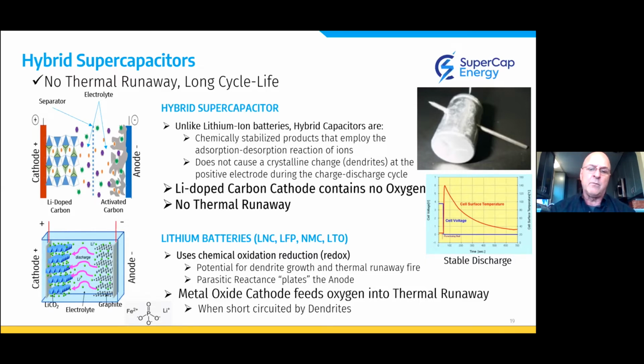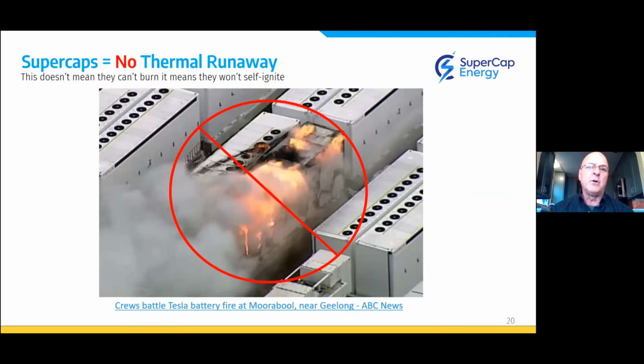But metal oxide, when it breaks down, does feed oxygen into a thermal runaway - that's one of the concerns people have. So supercaps have no thermal runaway, but that doesn't mean they can't burn. I have a 12-year-old bottle of scotch on the shelf, and if I broke it and lit it, it would burn. It's the same kind of thing - the capacitor could burn if you broke it open, but under normal operating conditions that never happens.